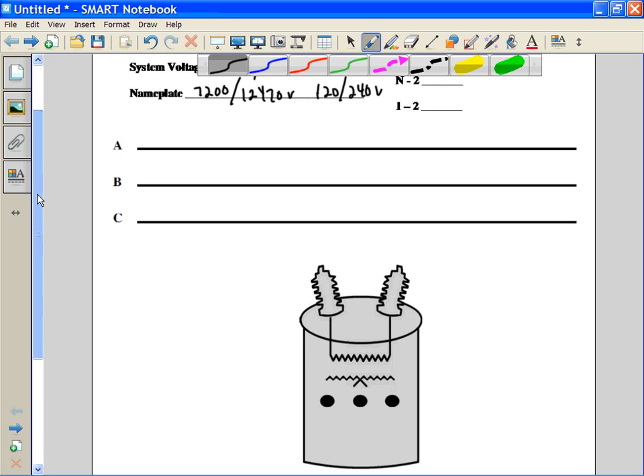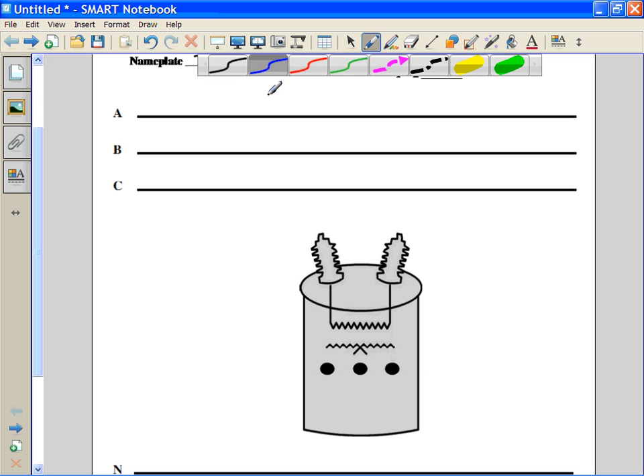So the one thing we always need to remember to do when we're drawing transformer connections is to make our polarity markings on all the transformers. We'll just assume this is an additive polarity transformer, which means the X bushings are X1, 2, 3 from right to left. And let's go ahead and make the primary connection.